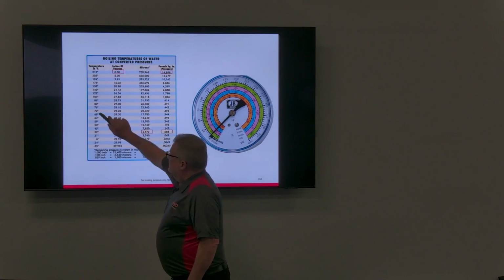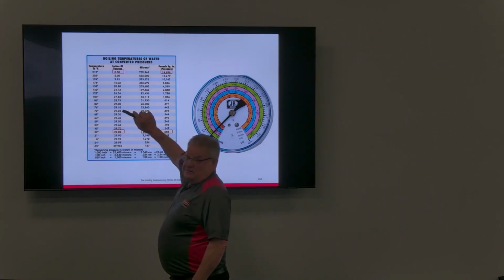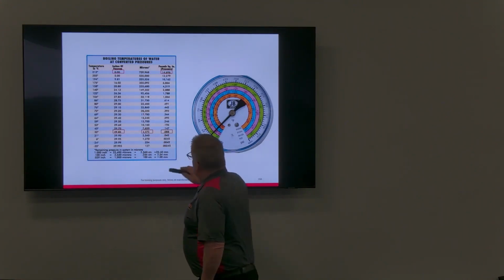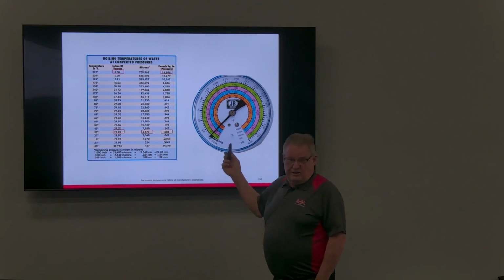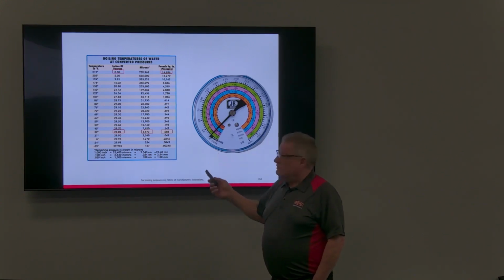So it's 70 and 72 in this room. I've got to get to 29.2 inch vacuum. On that gauge there, can you really tell you're at 29.2? No, because right now it's slightly out of calibration. It's going to read off anyways. That gauge is absolutely useless for vacuum.